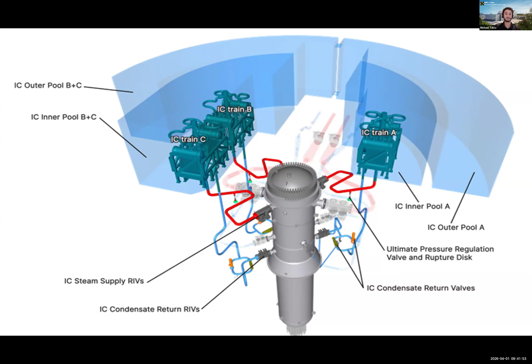They're meant to return the condensate back to the reactor in a closed loop with natural circulation, driven by the elevation and gravity. One train addresses the operational upsets, while two trains support loss of coolant accident mitigation and can sustain decay heat removal for 7 days without operator action. For more extreme scenarios, all three trains are credited and the above ground unpressurized pools can be topped up indefinitely using simple transportable water resources.